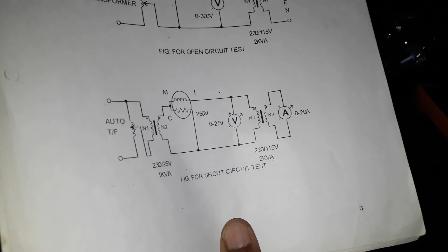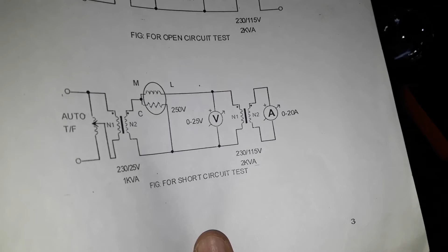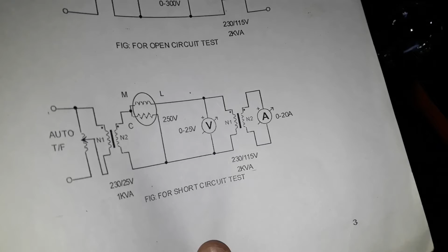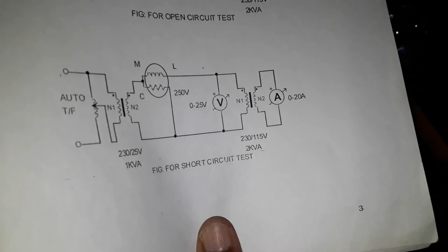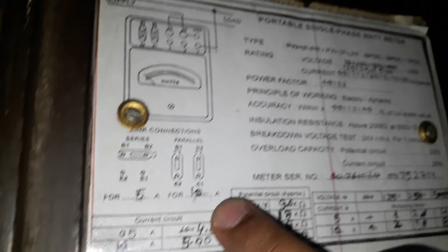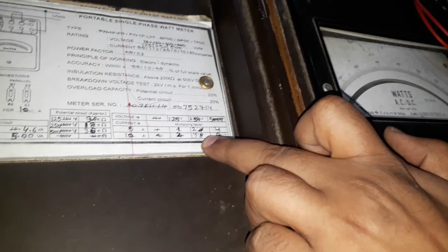So the wattmeter rating has to be selected according to the current expected. On the LV side, the rated current of the transformer is 17.6 amperes, so the current will reach up to 17.6 amperes, and on the HV side, on the 230 volt side, it will be exactly half of that. So we have chosen a wattmeter whose rating is 10 amperes. Earlier we were using the wattmeter at 1 ampere rating. Now the rating of the wattmeter is 10 ampere, and accordingly its multiplying factor will change. Instead of 2, it is now 4.